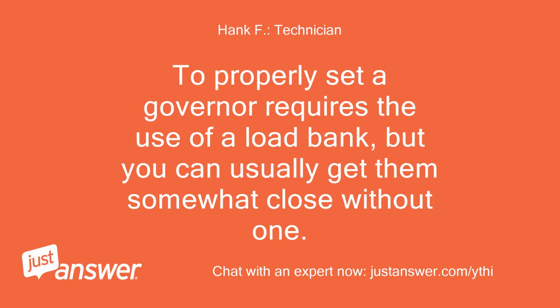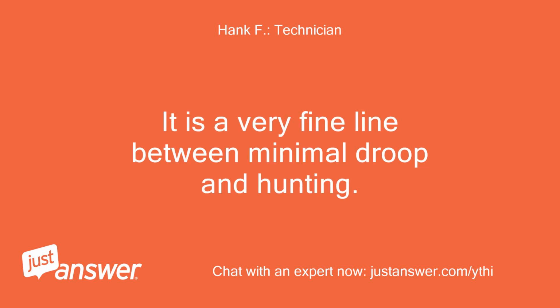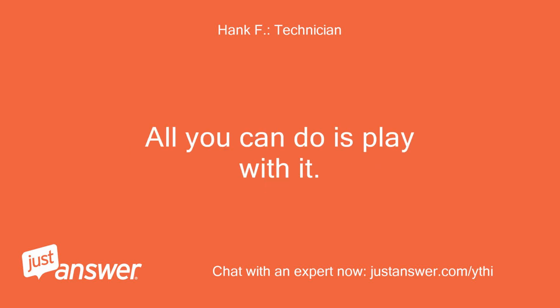To properly set a governor requires the use of a load bank, but you can usually get them somewhat close without one. It is a very fine line between minimal droop and hunting. All you can do is play with it.